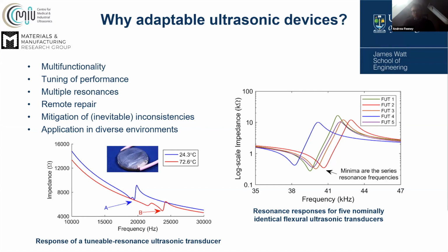So, for example, an ultrasonic device used for orthopedic surgery will be designed to operate at a precise frequency, to operate on the tissue for whatever is intended. In order to do this, these devices tend to involve very careful control of geometry and material properties to precisely tune these parameters. And these parameters include resonance frequency, amplitude, and there is often very little room for error, and that can often limit application performance.